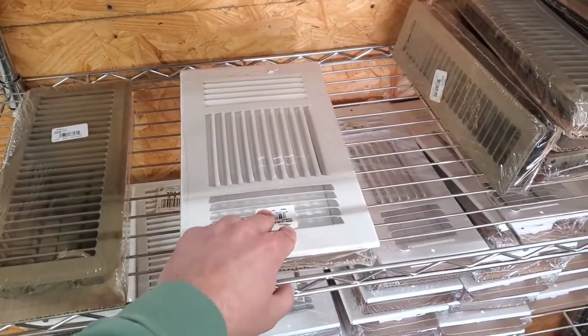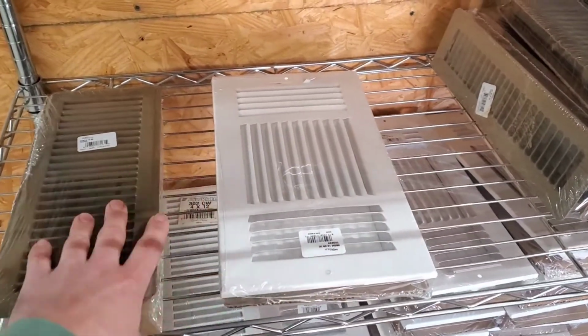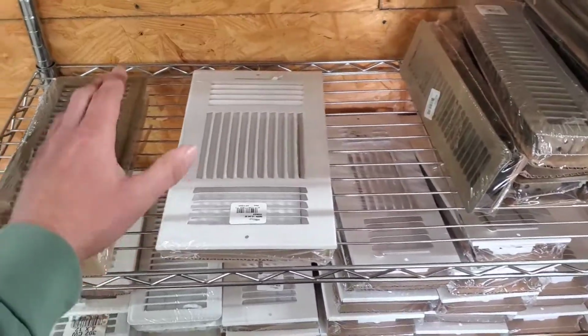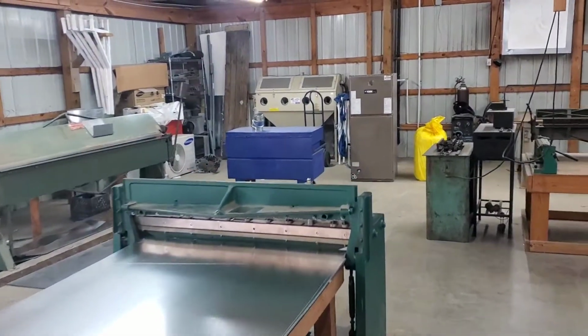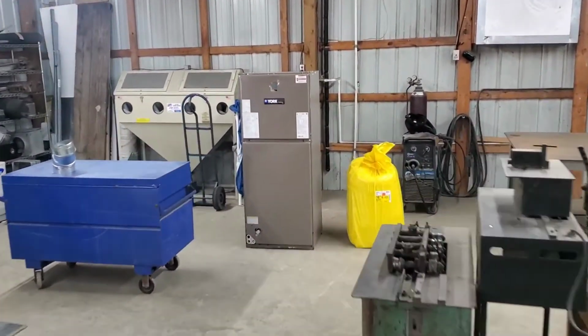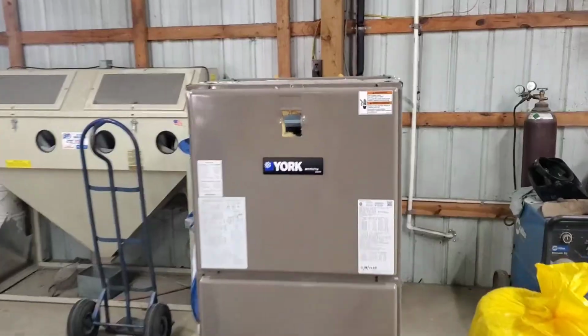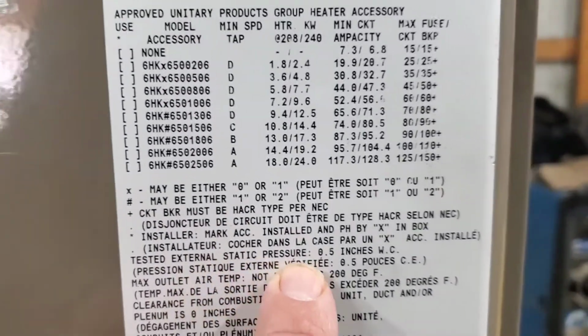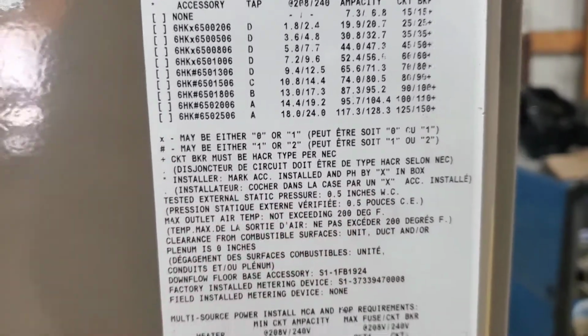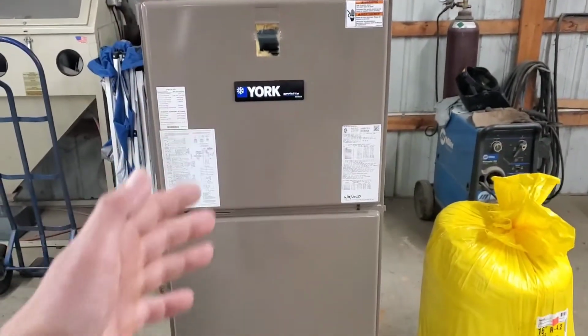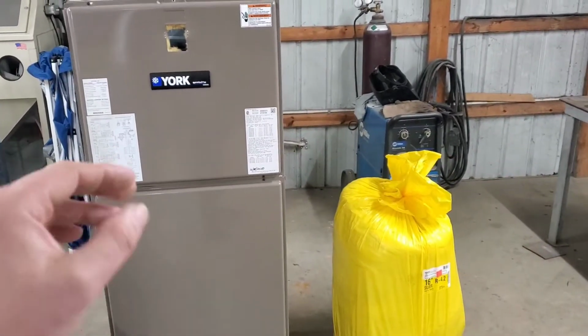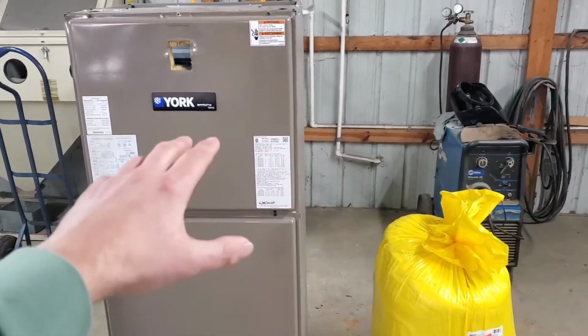Make sure you never close these supply vents, because if you do, you create more static pressure. And static pressure is something that you need to know about, because just like this air handler over here in the shop, there's a recommended static that the manufacturer recommends that you operate this equipment at, okay? I'm gonna show you that right now. Tested external static pressure, 0.5 inches of water column, okay? So if you go beyond that with the static pressure, you're not gonna have good performance out of the system, and then you're going to degrade the components.